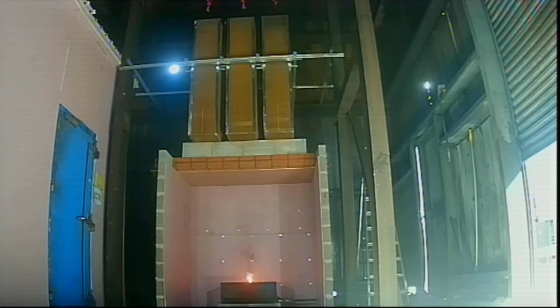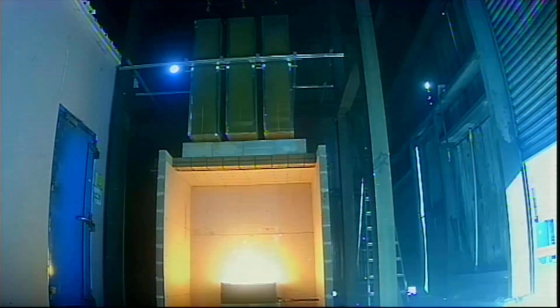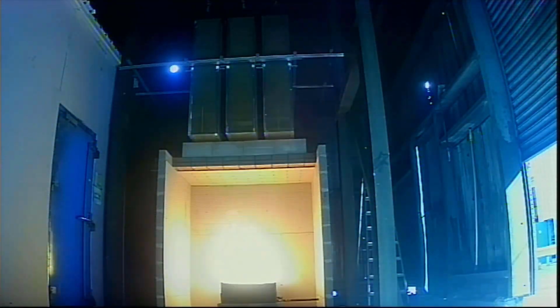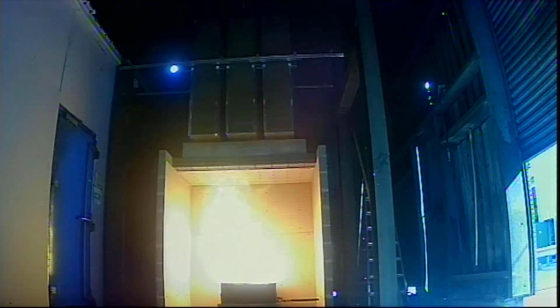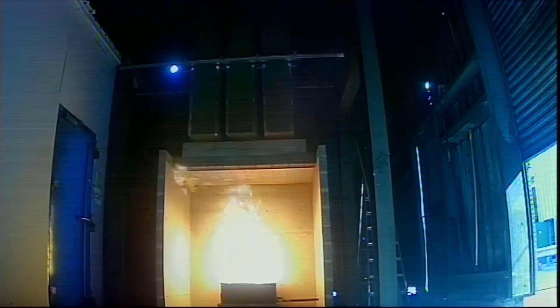We worked with BBA and Ibstock. BBA is the British Board of Agrément, to design an appropriate test for them because there wasn't an appropriate test standard. It was proposed that a fire replicating a room in flashover, venting through a window should be used, and after a few discussions back and forth, it was decided that a gas-controlled fire, maintaining the temperature at the underside of the lintel above 600 degrees for 2 hours would be used.